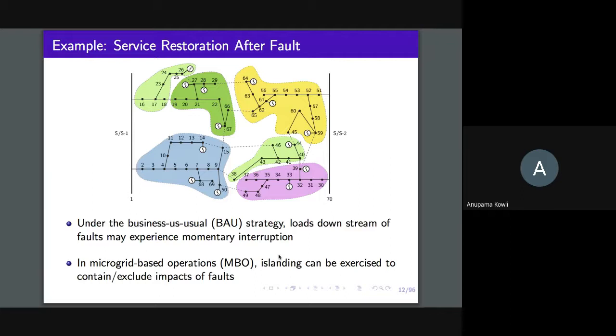So in doing this whole process, what do we have to do? We basically have to de-energize this entire feeder, isolate 5-6, and then reservice and reroute power through any of these switches, 14-15, 15-67, and so on. In doing this, there's a momentary interruption that all the nodes face, because this whole process has to go through de-energizing, then re-energizing, and then potentially rerouting the power.